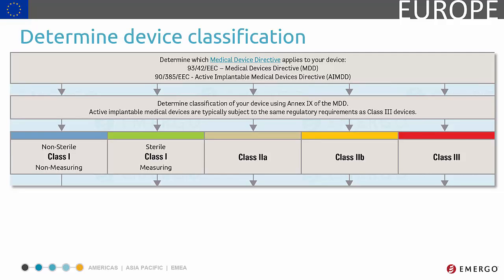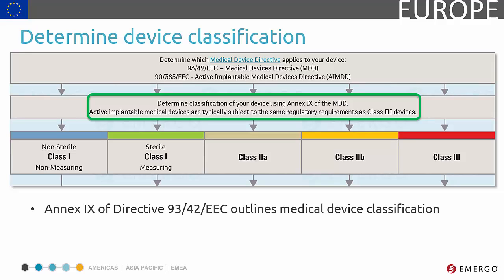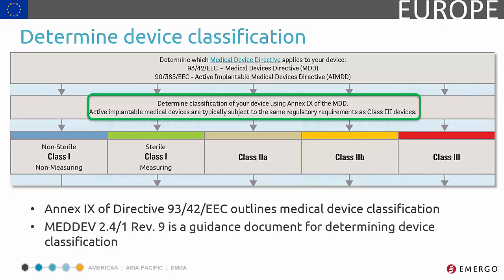Device classification depends on 18 rules outlined in Annex 9 of the Medical Device Directive. There is also a guidance document which specifically covers product classification. It provides detailed explanations of each class and examples of how intended use, duration, level of invasiveness, and area of effect are calculated. It's an invaluable tool that should not be overlooked.